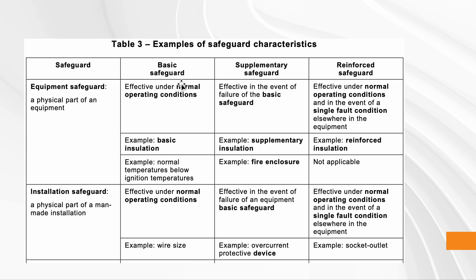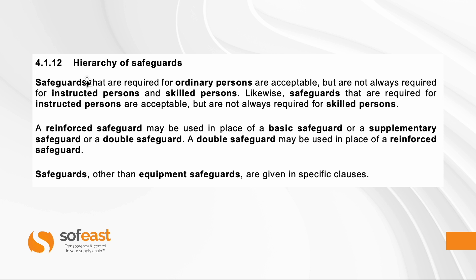For example, the basic safeguard is to ensure temperatures remain below dangerous levels — using a fan and vents to keep things cool. But if the fan stops working or the vents are blocked, you also need a fire enclosure so that if fire starts inside the product, it is contained. If the enclosure melts or breaks too easily during a fire, you don't have an effective supplementary safeguard.